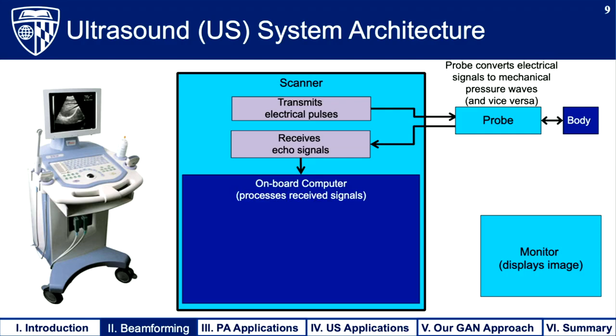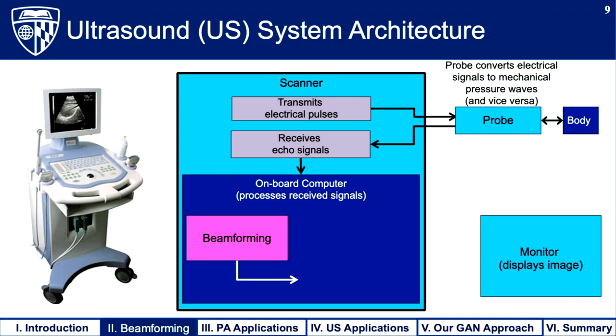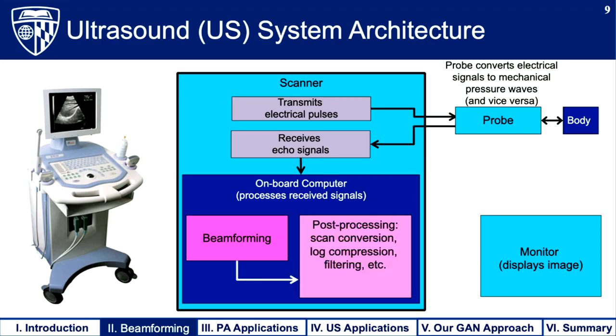The first step in the processing chain is beamforming — you can think of beamforming as the first line of software defense against a poor-quality image. After beamforming, the signals undergo further post-processing such as scan conversion, log compression, and filtering, and finally the image is ready for display on the monitor.